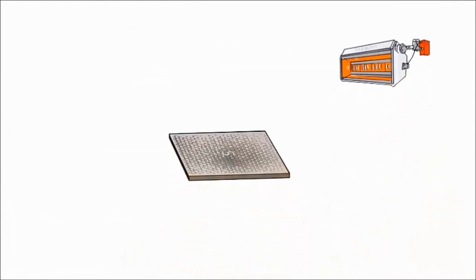With plaque heaters, the combustion takes place on ceramic tiles, which then radiate the infrared energy. And because this is highly efficient, plaque heaters are usually appropriate for buildings of over 6 metres height.